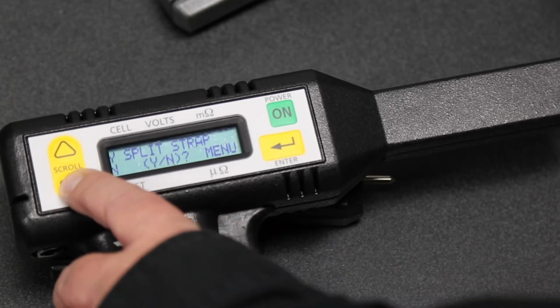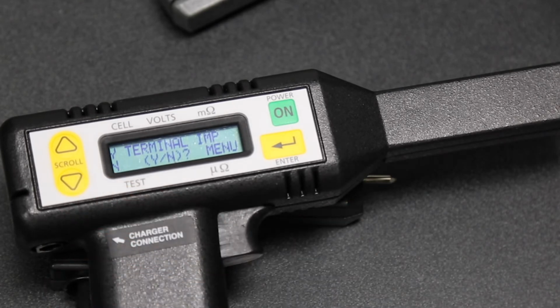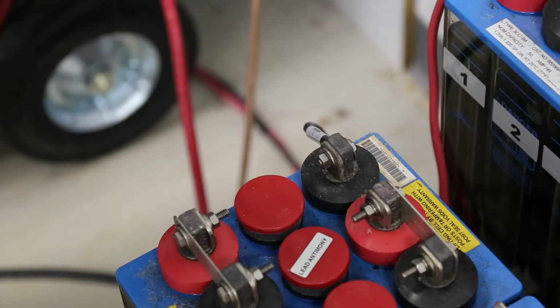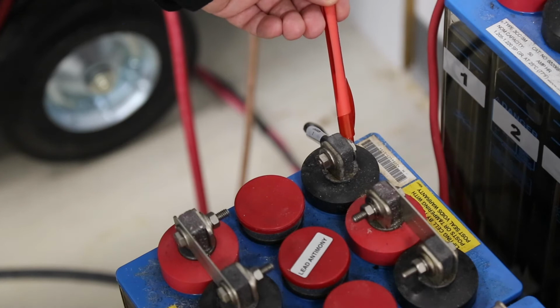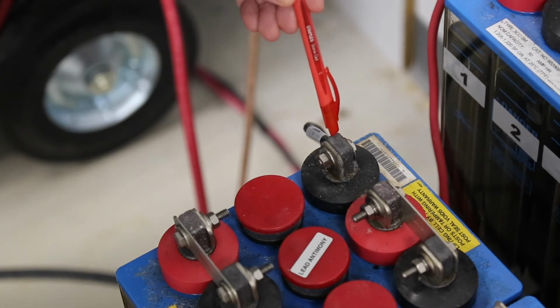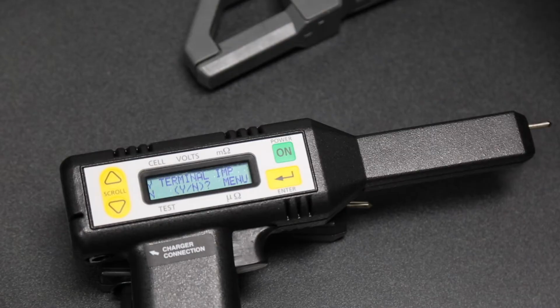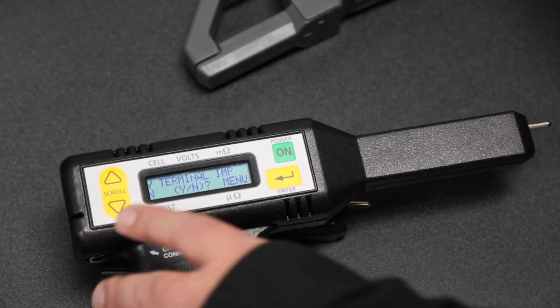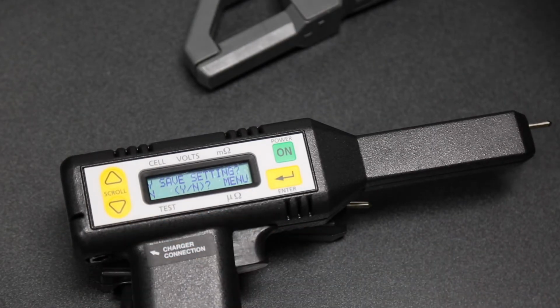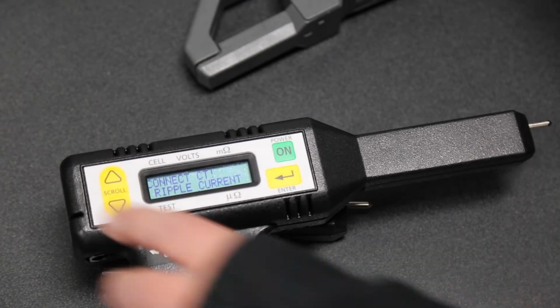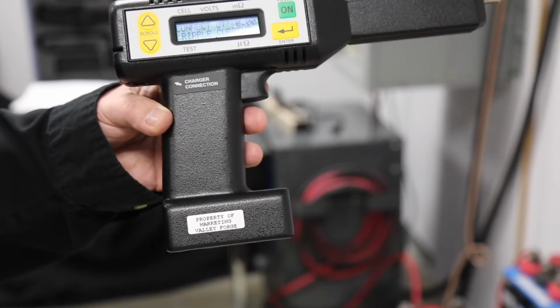The last thing I am asked is if I wish to measure terminal impedance. This is the value from the charger lead to the first terminal. This is sometimes required for standards testing. I am going to select No. I can now save the settings and start my test. The receiver now prompts me to connect the CT.